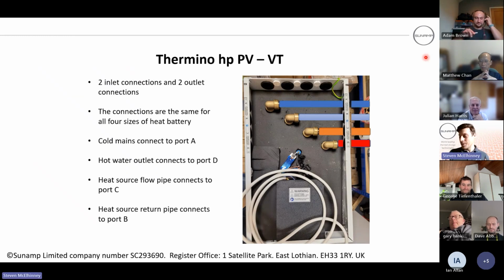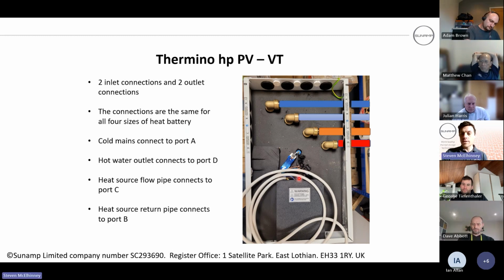I never designed it. This is what we have. Going forward with the new product, we will have just a single, one pipe for every application, basically. Whereas this is what we have at the moment. Why it's like this just now is our controller has its set points, and the way the unit's discharging and recharging, that's how the controller recognises it from top to bottom or bottom to top. With the new product we're going to be releasing, we're going to have the same connections for all the units, but it's going to be a different controller that will be able to recognise the different set points all by itself, so that you won't have to figure all this out.